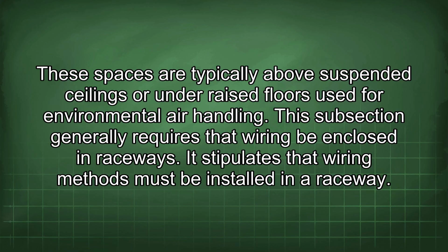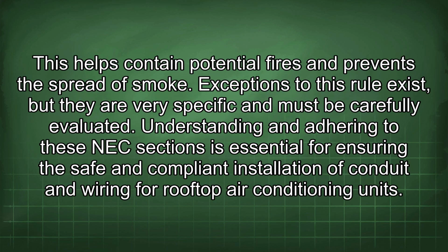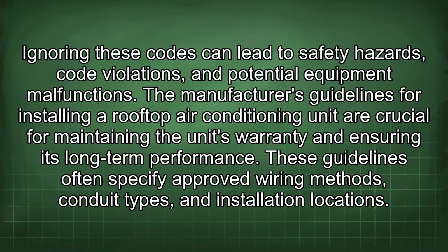It stipulates that wiring methods must be installed in a raceway. This helps contain potential fires and prevents the spread of smoke. Exceptions to this rule exist, but they are very specific and must be carefully evaluated. Understanding and adhering to these NEC sections is essential for ensuring the safe and compliant installation of conduit and wiring for rooftop air conditioning units. Ignoring these codes can lead to safety hazards, code violations, and potential equipment malfunctions.